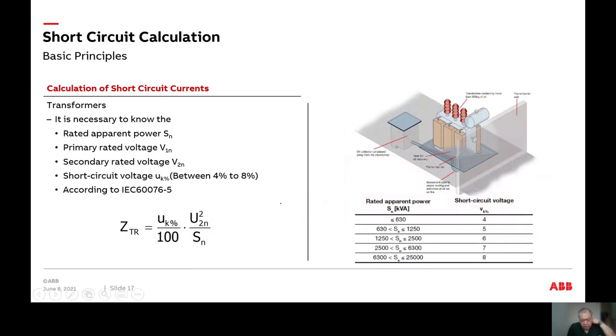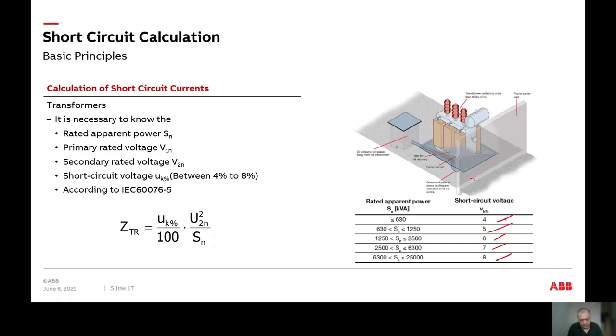For transformers, the short circuit voltage — denoted as Uk percentage — is usually between 4 to 8 percent depending on the size. Smaller transformers are around 4%, 630 kVA to 1.2 MVA is about 5%, up to 2.5 MVA is 6%, 6.3 MVA is 7%, and 25 MVA is 8%. Different transformer sizes have different short circuit voltages, so we need to take note of that.